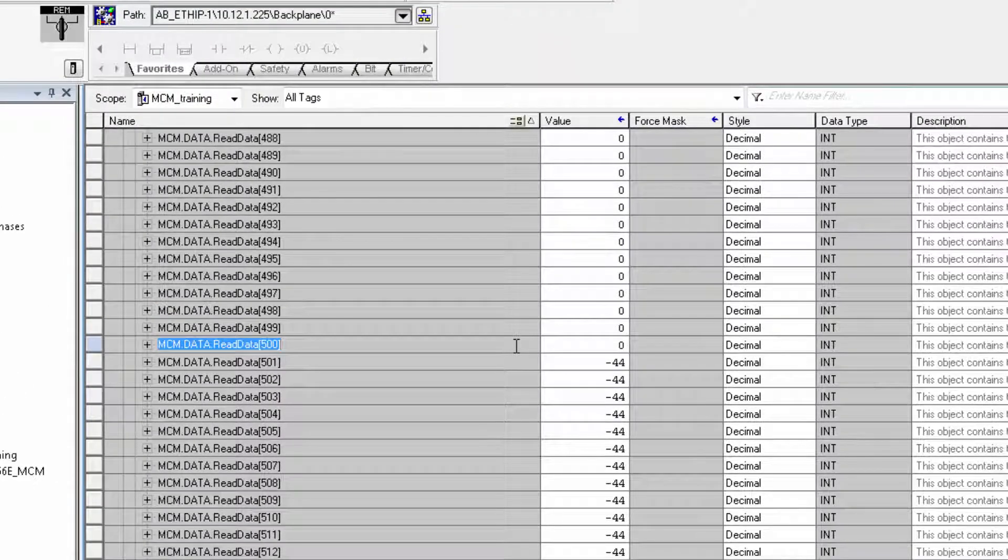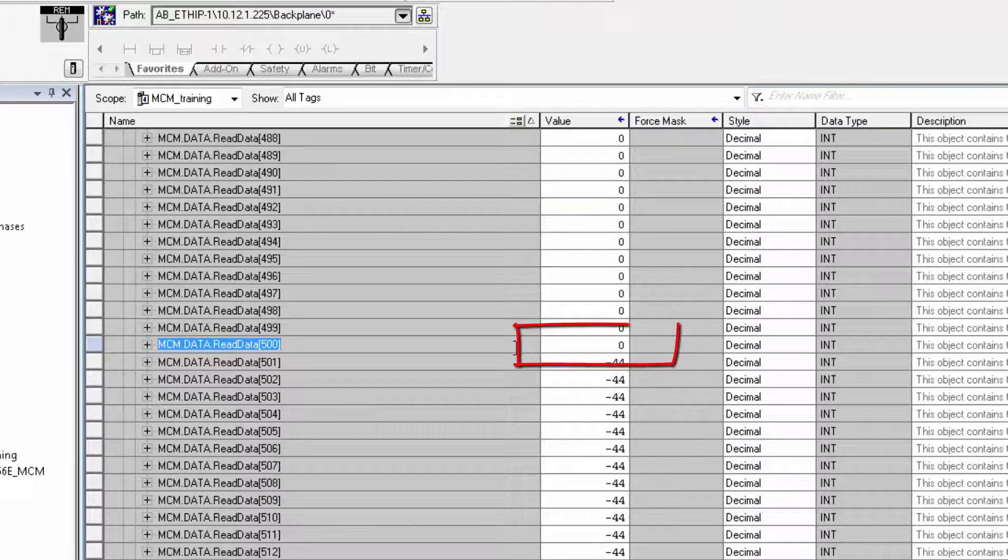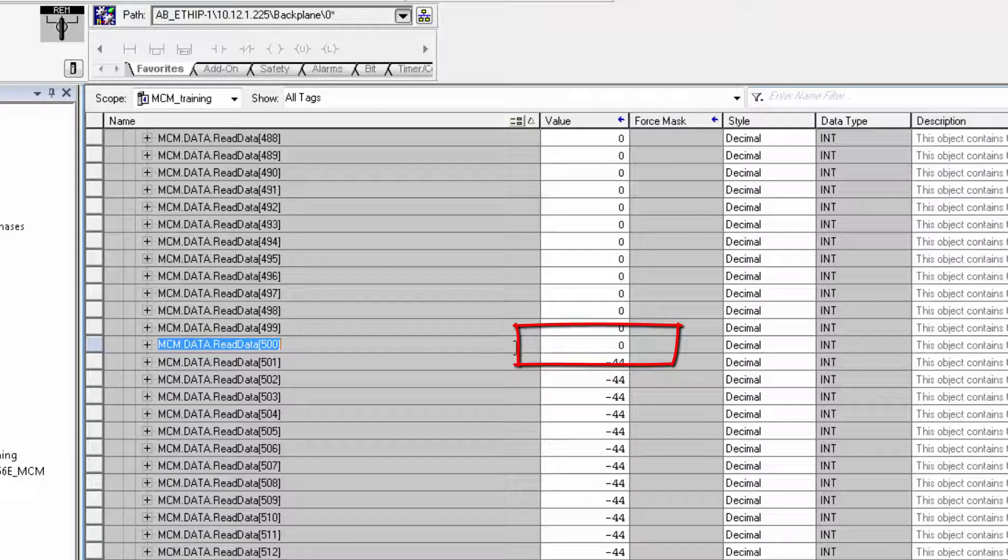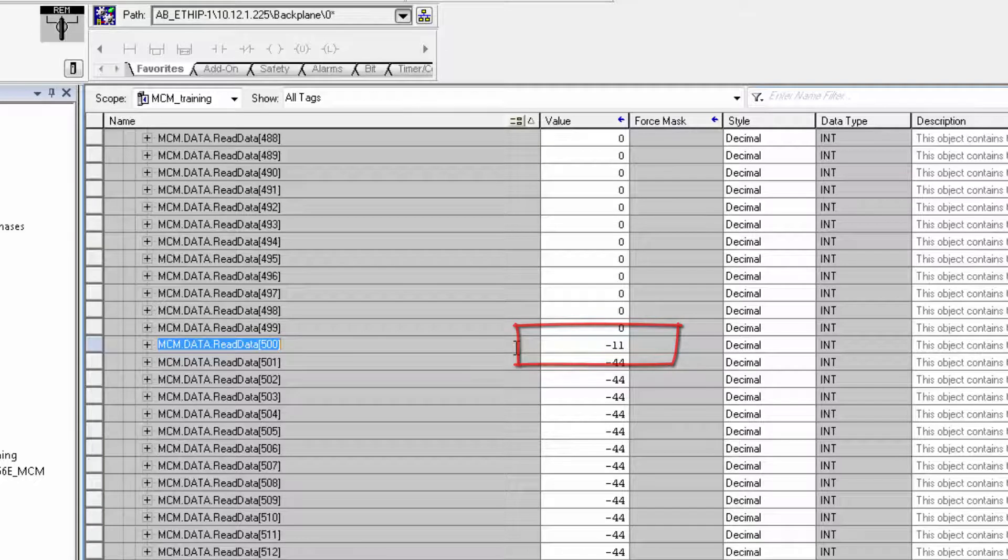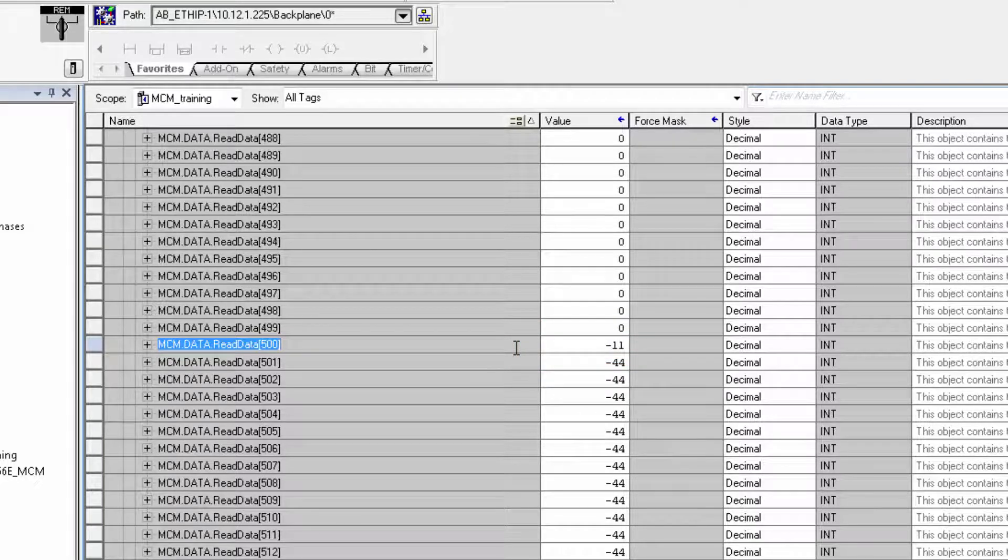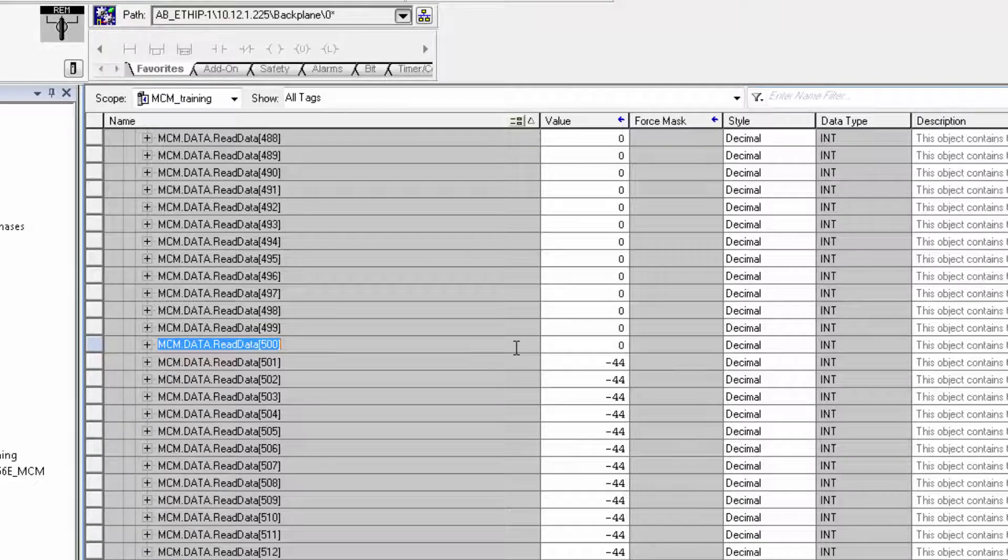So if I unplug the cable from the slave device, I can see the tag turns to a negative 11, which is a common Modbus communication error code means the slave device is not responding. If I plug the cable back in and wait for a moment, the tag returns to a zero, meaning all is well.